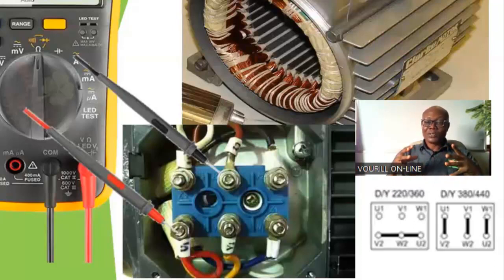They are expected to be of the same value. So the one that is shorted within, burnt inside, you see that the value will be far, far reduced, because it has been burnt and shorted within. All of those will give you an idea as to the condition of the electric motor. So when you notice any such thing, definitely the solution to that motor is repair or complete overhaul.